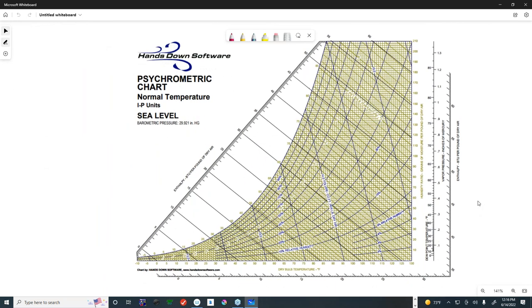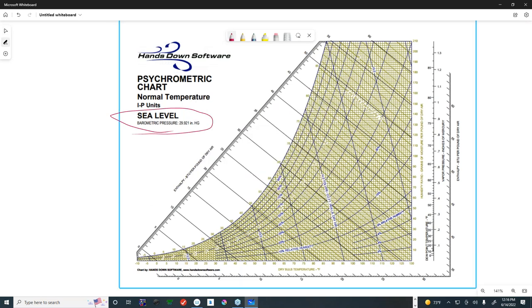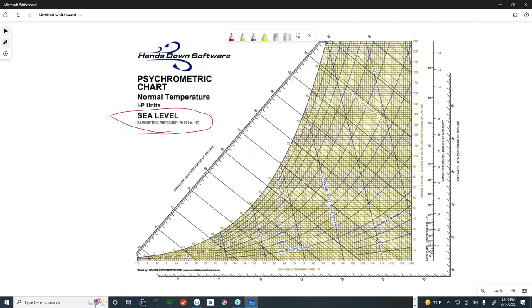that the psychrometric chart is at the right atmospheric pressure. This particular psychrometric chart and all the ones we're going to look at today are considered to be at sea level, which has a barometric pressure of 29.92 inches of mercury, which is also the same as 14.7 pounds per square inch absolute. So that's the very first thing we need to know: the atmospheric pressure. All the psych charts we're looking at today, we're going to assume we are at sea level in this particular case. Okay, so we're going to try our eraser here.